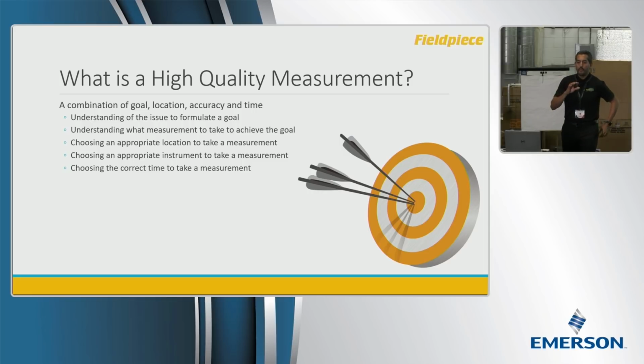Secondly, after we understand the issue, we need to understand what type of measurement we need to help us troubleshoot that issue. So if I suspect that there's low incoming voltage to a system, I'm not going to take an amperage reading. We have to match the measurement to the issue that we're looking for.